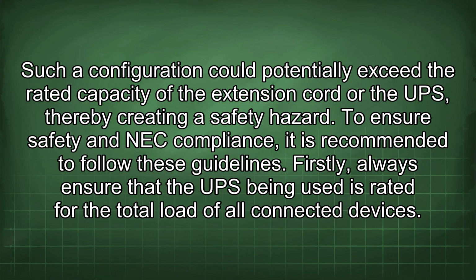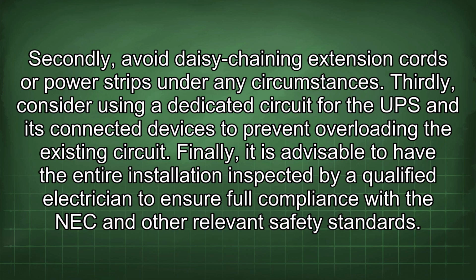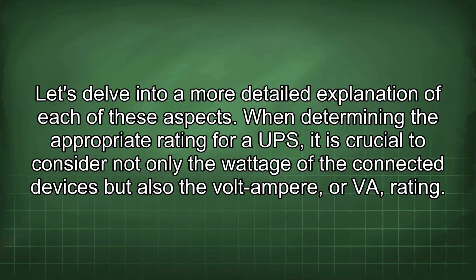Firstly, always ensure that the UPS being used is rated for the total load of all connected devices. Secondly, avoid daisy-chaining extension cords or power strips under any circumstances. Thirdly, consider using a dedicated circuit for the UPS and its connected devices to prevent overloading the existing circuit. Finally, it is advisable to have the entire installation inspected by a qualified electrician to ensure full compliance with the NEC and other relevant safety standards. Let's delve into a more detailed explanation of each of these aspects.